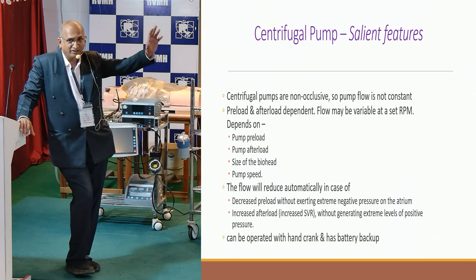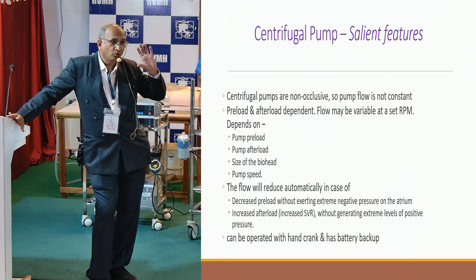Now, why am I emphasizing this? Suppose I get a call from someone in some other part of India. They call me and say, okay, my RPM is 7000 and flow is 3 liters. I have to first ask which machine you are using. It has to be Medos, because that's the only possibility. With 7000 RPM you get a flow of only 3 or 3.5 liters. That is not possible in any other machine. So whenever you are talking about the RPM flow ratio, you should know which machine you are using. Okay, fine.